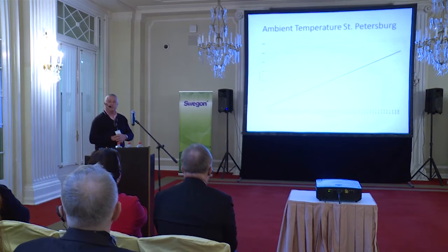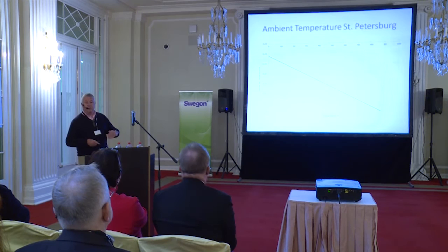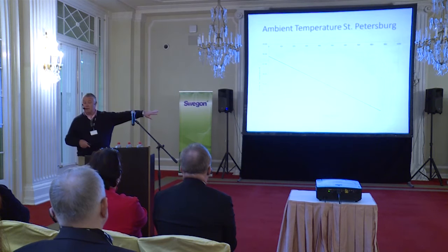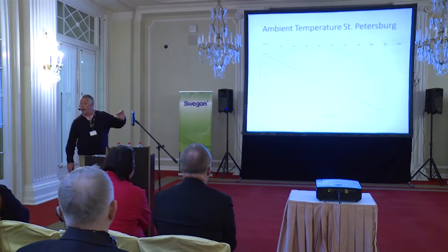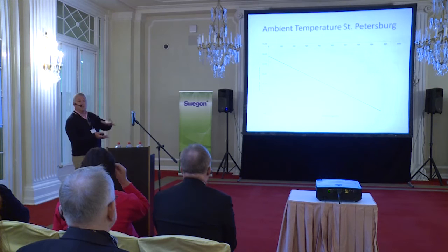The reverse happens during the winter. We start off at minus 27, 26 degrees, and it goes down, so at the top it's minus 32. So now we've got two different dynamics going on with our building. Our heating system, as we go up the building, needs to increase inside. Our cooling system from the transmission can decrease as we go up the building.